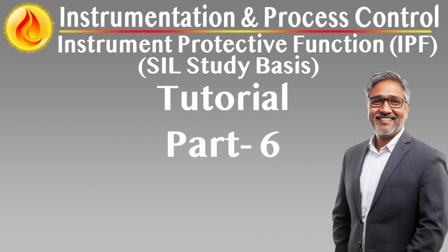Post-maintenance reinstatement and function check. Restoration, confirmed by both maintenance and operations. After maintenance is completed, both the responsible technician and control room operator must confirm the override has been removed and the IPF is restored to normal function. Operational verification prior to restart or load increase.